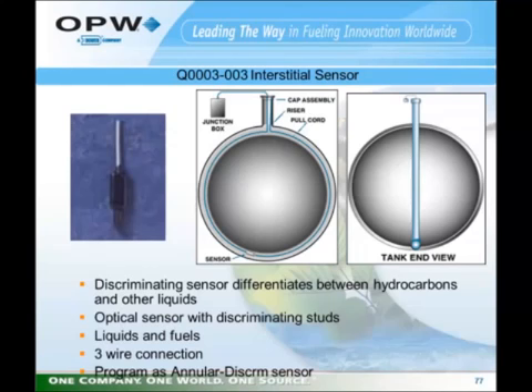This uses a 3-wire connection and is programmed as an annular discriminating sensor in the sensor programming in the unit. If you wish to test this sensor, you must keep in mind that this sensor is designed to work in the dark. If you try and test this sensor above ground in ambient sunlight, it will not go into alarm because the ambient sunlight will be detected by the sensor's optical detector. What you would need to do is put this in a dark space, covered with a shop rag, something like that, so that you can restrict the light going to it to test to see if it will detect liquids.